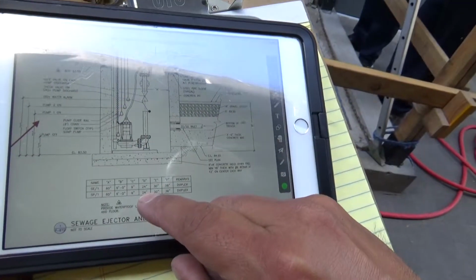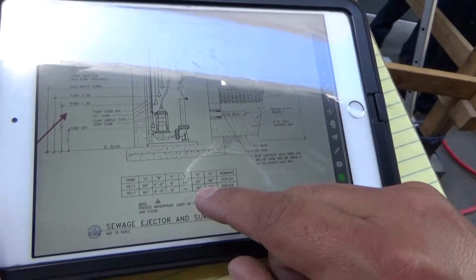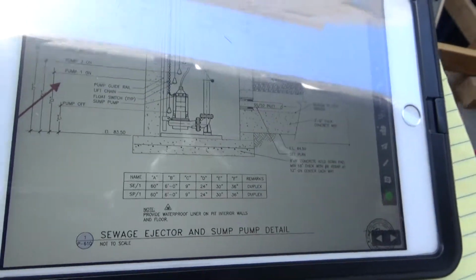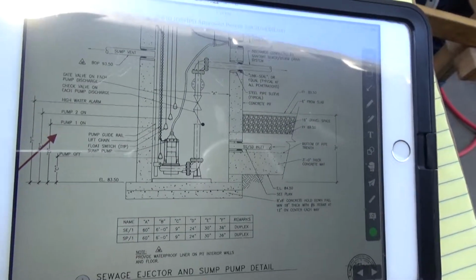Pump 1 comes on at 24. Pump 2 comes on at 30. And the high water alarm is at 3 feet. Cool. That's where those are set now.